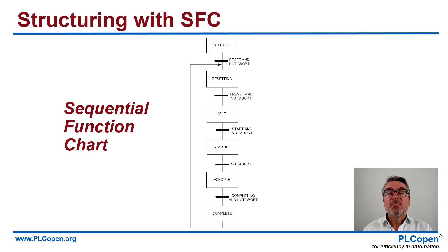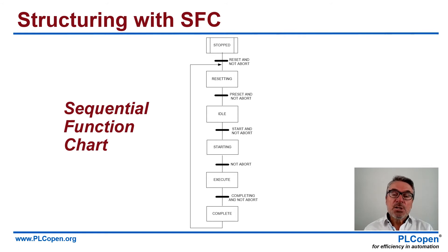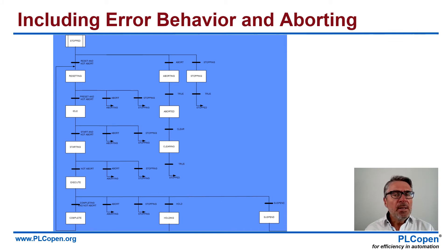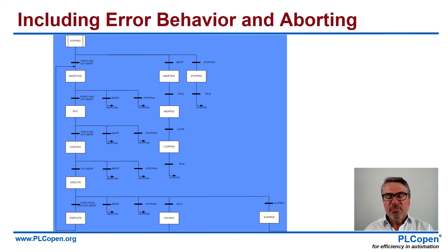With structuring, you decompose your problem into sequences and steps. Within IEC 61131, there is a structuring tool called Sequential Function Chart for this. You see a loop where you execute a process and know how it continues. You identify all the sequences and all the different steps, including the error behavior and the aborting situation. Normally the normal behavior is simple — it is the exceptions where you need to invest your time and have your focus.